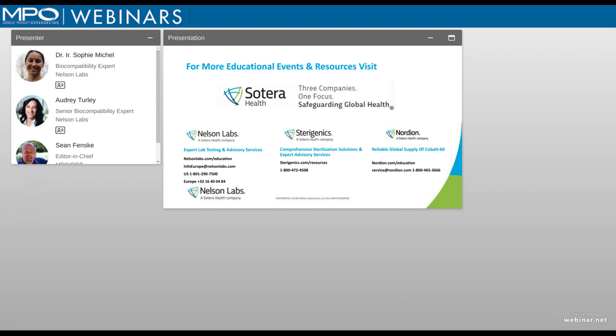Okay, we have another one. If the medical device is a biodegradable orthopedic implant, is in vivo mandatory? That's a great question, and we honestly don't know at this point if you would have to do in vivo. I think the in vitro method is just as applicable for an implant as it is for a surface device because it doesn't discriminate against that application, and the barrier system there is sensitive enough for an implant in the tissue. So I do think that it's appropriate.